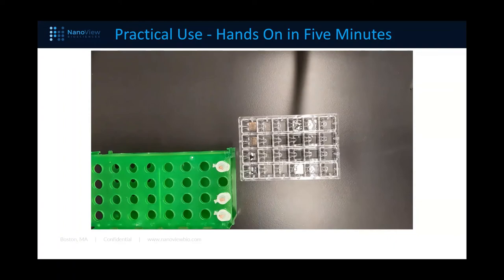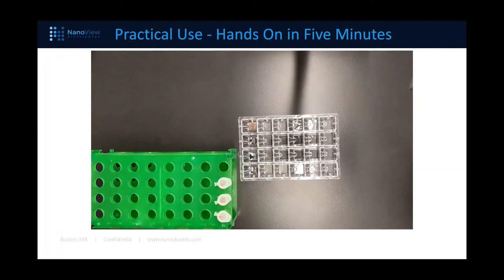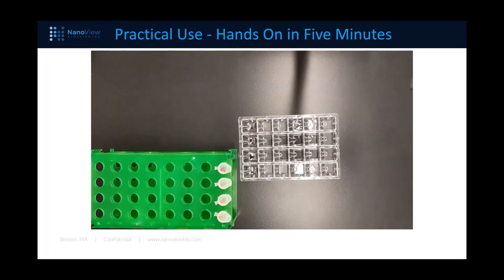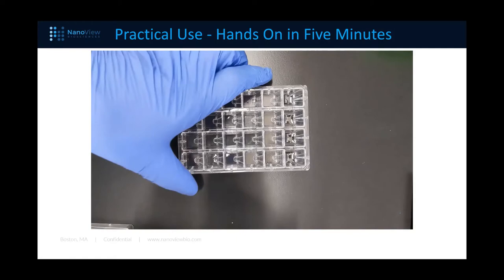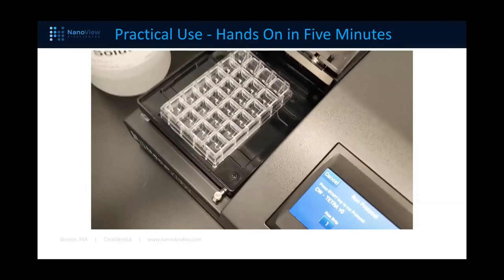Loading up the samples is pretty simple — we do a one-hour incubation. We load the samples and then one hour later put them in the washer. It only takes about three hours to get data from anywhere from one to 24 samples; it doesn't add a lot of time to run more than one sample. Utilize that available time to maximize instrument productivity. You load four strips here, wait the one-hour incubation, and then set them right into the plate washer. After this stage, you only have a couple of interactions with them to load other reagents, mainly for customization.